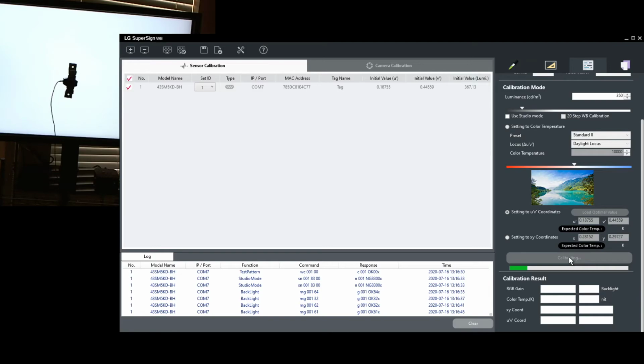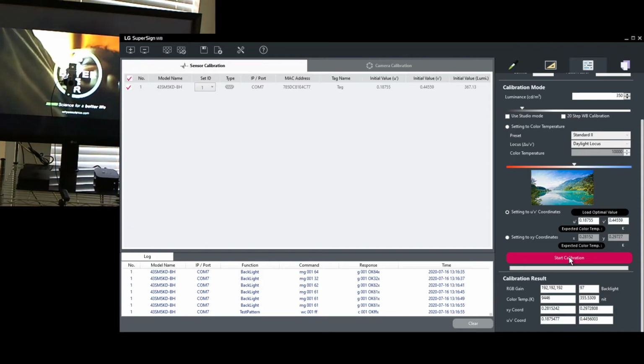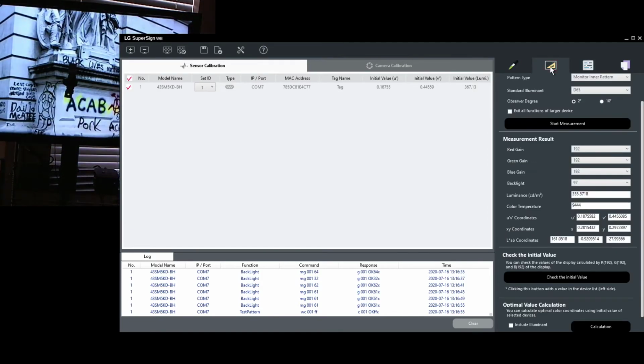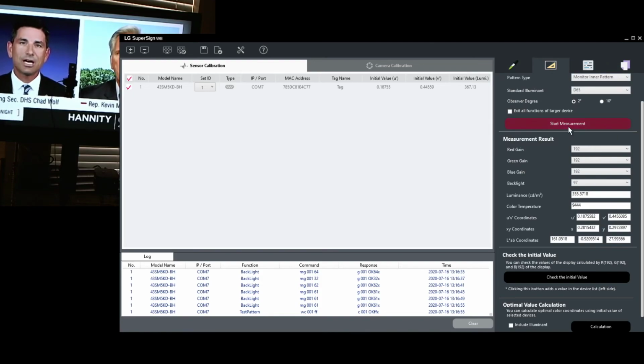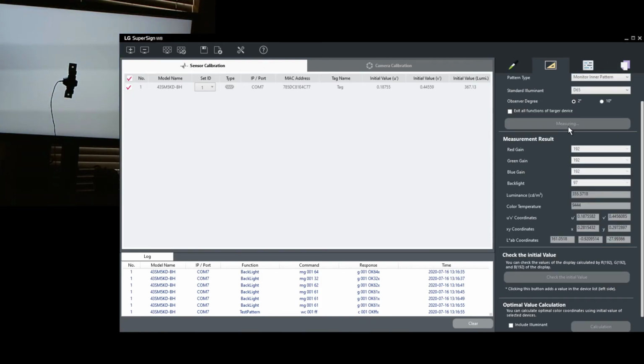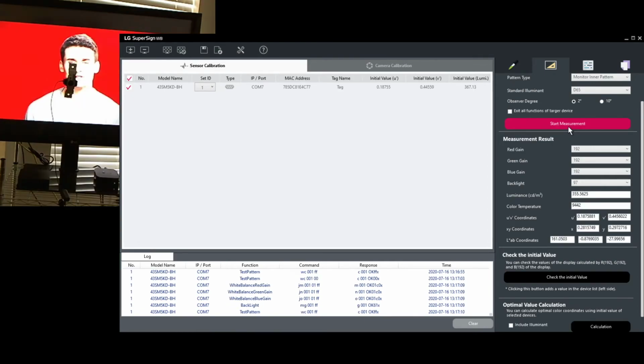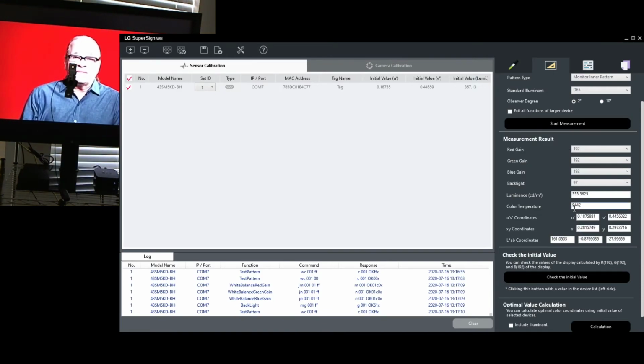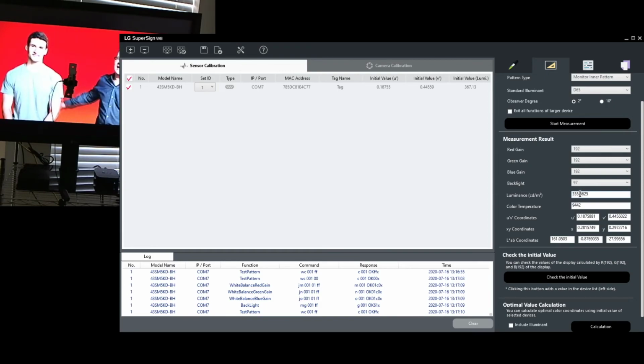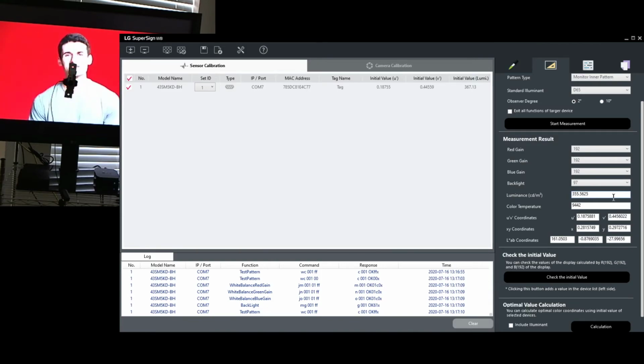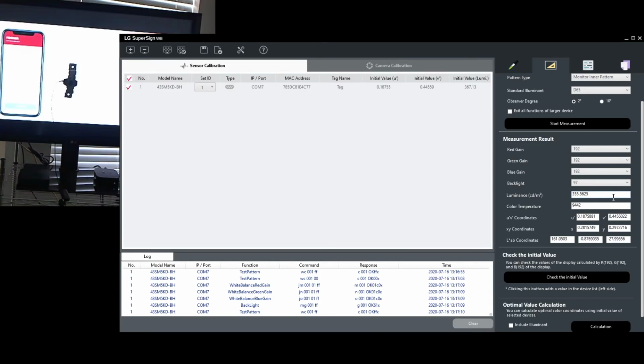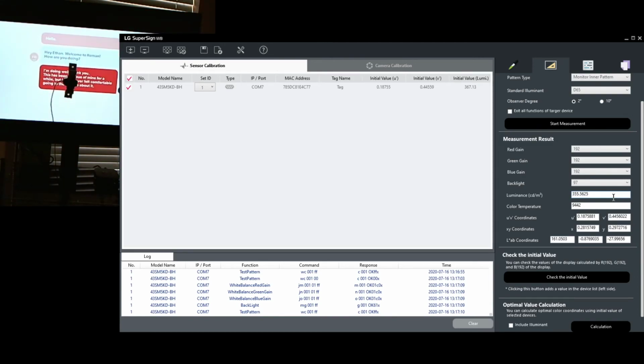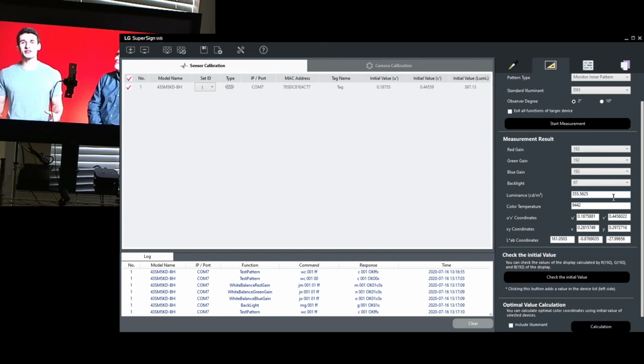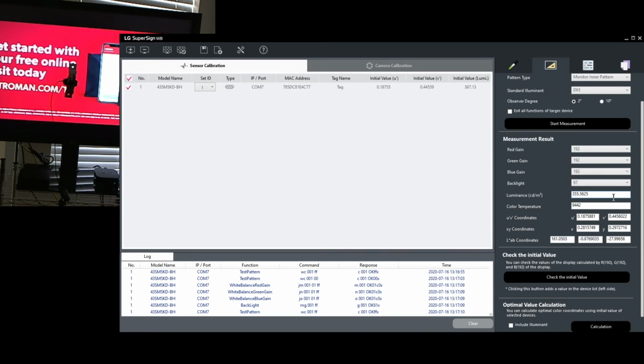So as the process continues calibrating the display and completed, now we can go back and just remeasure our values. 355.5718 for luminance, 9444 for color temperature. So let's see what kind of change we get. We went from 9444 to 42, 355.5625 from 57.18. So there was just a slight variation within that RS232 and the LAN. Now if we went back and did it LAN again, LAN would put it back to just about the approximate identical value as the previous values.